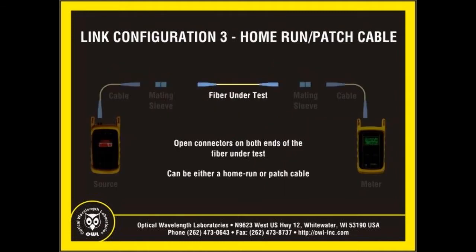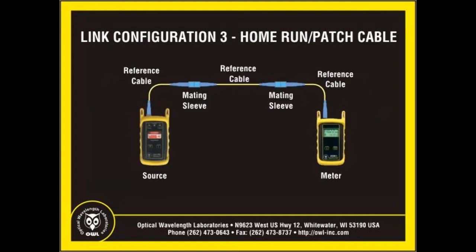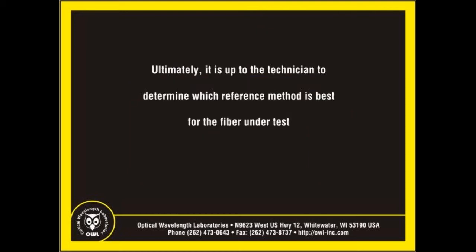The third link configuration does not include any mating sleeves in the link under test, so both ends of the fiber are just open connectors. This is typically referred to as a home-run cable, but a patch cable also fits this description. What remains from the test configuration is: the source, a cable, a mating sleeve, another mating sleeve, the second cable, and the meter. Simply add a third reference cable in between the mating sleeves to connect using the three-jumper method and set your reference. Once the reference has been set, remove the center patch cable and insert the home-run cable or patch cable under test. Ultimately, it is up to the technician to understand how to look at the link under test and choose the best reference method for the job at hand.